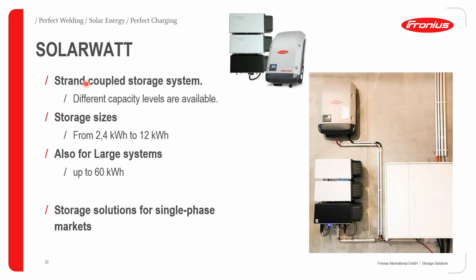So the SolarWatt system is a string coupled storage system. We have different capacity levels available. It's based on a modular approach. You can just increase the number of modules to increase your DC storage. The storage sizes vary from 2.4 kilowatt hours to 12 kilowatt hours, but you can also go up to 60 kilowatt hours. Again, due to these size variants, this is mainly going to be a target for single phase markets.